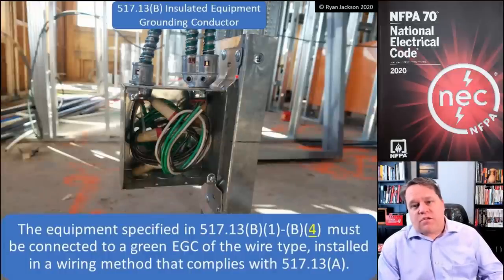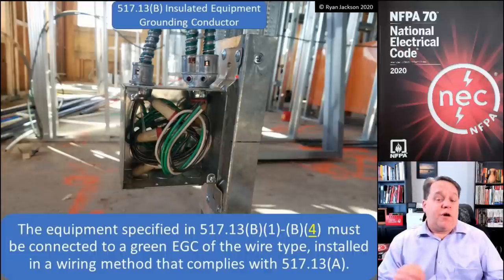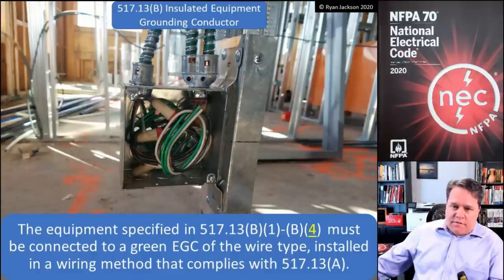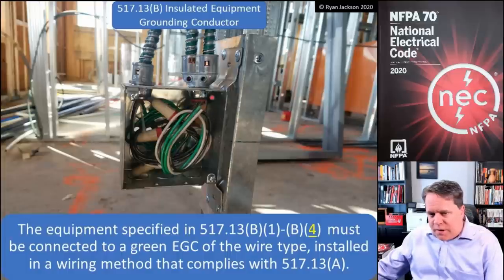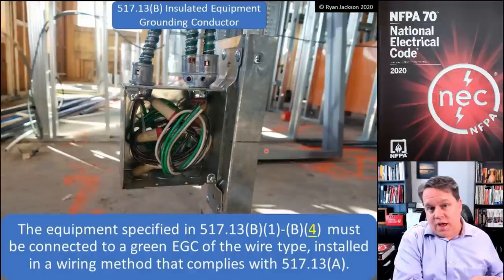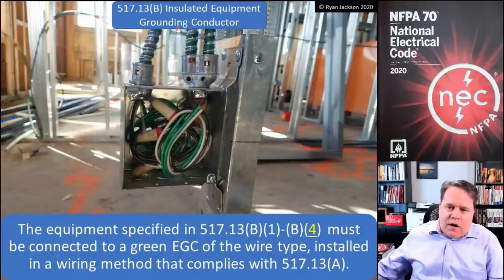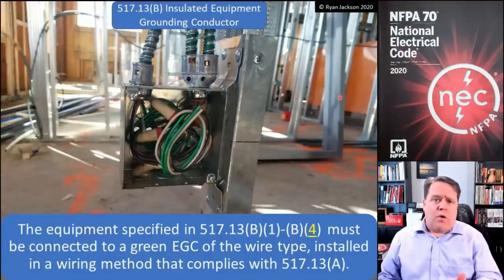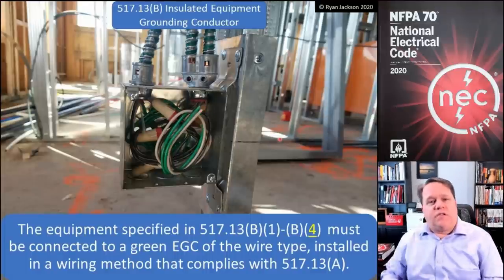Moving to section 517.13B, it talks about an insulated equipment grounding conductor. It says the equipment specified in items 1 through 4 must be connected to a green equipment grounding conductor of the wire type, installed in a wiring method that complies with A. So I have to have both: a special cable armor and a green wire inside of it. AC cable satisfies 517.13A because all AC cable has that aluminum strip, and the green wires inside satisfy 517.13B.